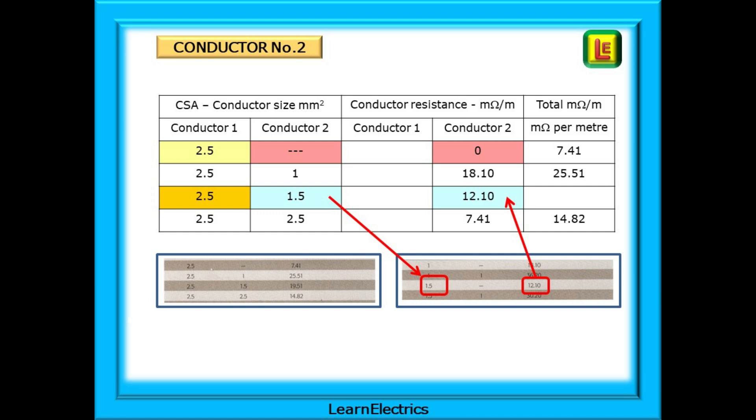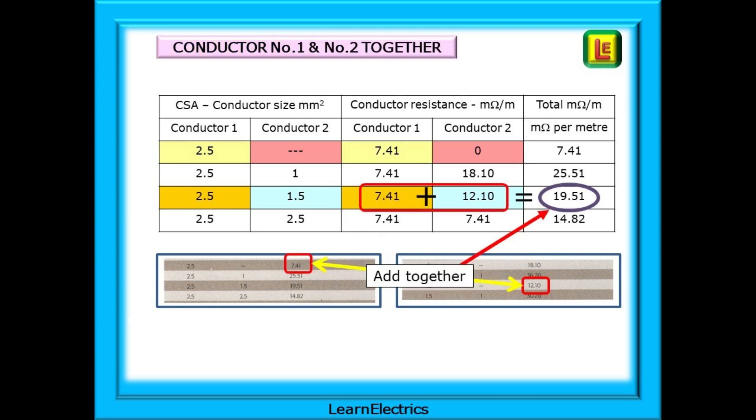This is 12.10 milliohms per meter and this can now go into the column for conductor number two. So we have 7.41 which takes into account the length of conductor number one and we have 12.10 which includes the length of conductor number two. Added together, they come to 19.51 milliohms per meter length measured just one way. There's nothing more for us to do. It's all included in the numbers in the table. So if this was 10 meter cable it would be just 19.51 multiplied by 10 meters and divided by 1000.